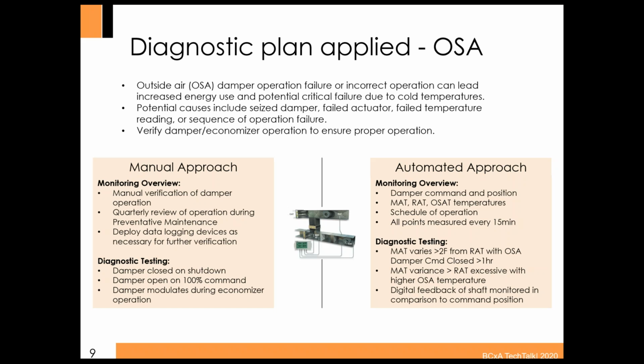So from a monitoring overview, thinking about the question first, we're now looking at what data we need in order to answer the question: is that economizer working appropriately? So we're looking at the demand, the damper command position. If it's available, we're looking at the actuator position for comparison. We're measuring the significant temperatures: mixed air, return air, outside air temperatures. We're looking at the schedule of operation. And we're monitoring that at least every 15 minutes. Depending on the system, you may choose something more frequent than that.